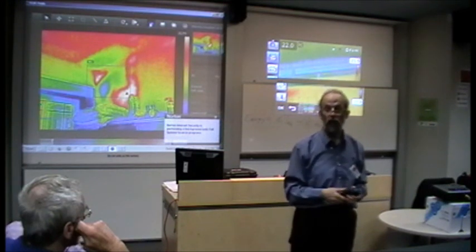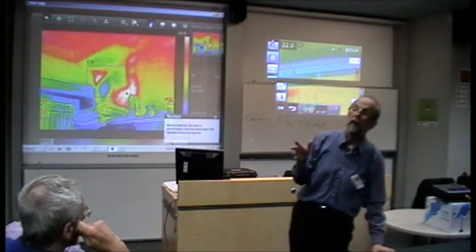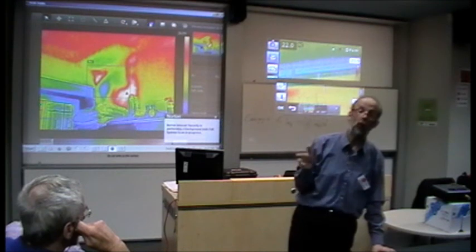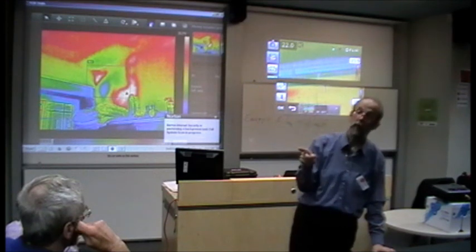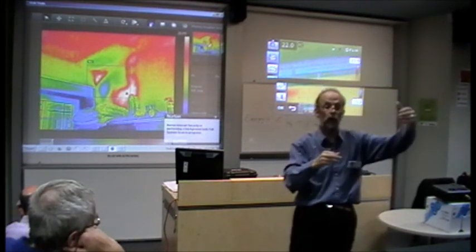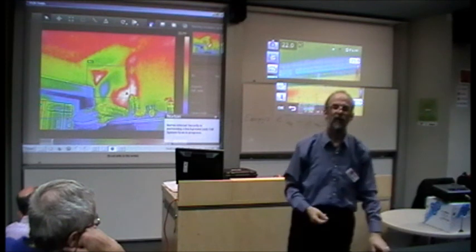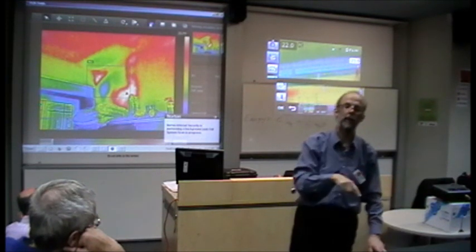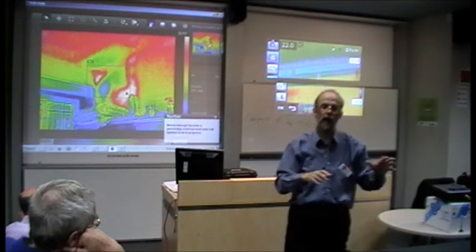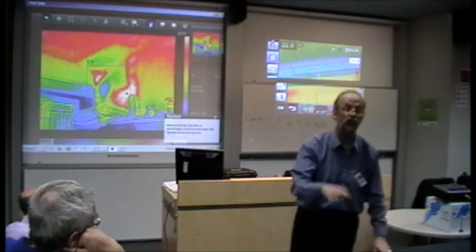You do have problems, and they talk about solar loading on buildings. They say that on masonry, the effect of the sun can remain there for up to 8 hours in some cases. So if you're looking from the outside, you really have a big problem, because you'll see areas which are looking hot, and it could be not because you've got leaks from inside where you've heated the house to the cold outside, it's because it actually heated up by the sun. Whereas on the inside, if you were allowing the house to be cold and just watching whether the heat's coming through, you could get away with using that. So you have to think very carefully about it.